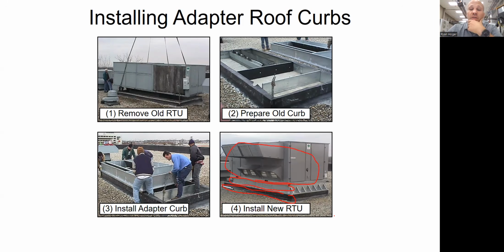This is really common to do. In order to do this, when you're replacing it, what normally happens is that whoever you're getting bids from for the rooftop, they go to the supplier of that rooftop unit and they say, hey, I'm taking off a Lennox model XYZ, whatever it is, and I'm putting on a Carrier or whatever model number. As you can tell, I work at a Carrier distributor, so it's always replaced with a Carrier. I'm putting on a Carrier ABC. And then they can go look up the dimensions of these two things and say, oh yeah, those things line up. Or no, dude, that's not even close. We need this adapter, right? So you've got to figure out what adapter fits between them.